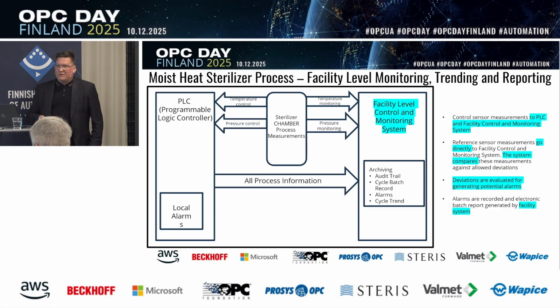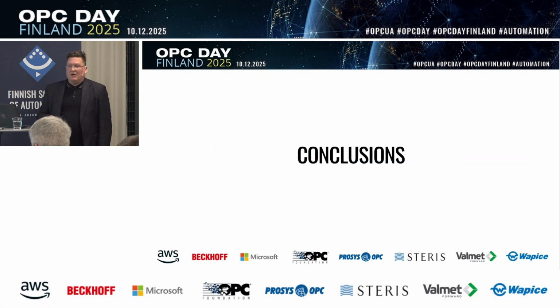From that perspective, this is what we are seeing as a sterilizer manufacturer - the possibilities that going to this kind of system with OPC UA gives to simplify sterilizers and focus on the essential. So that's basically our message on that.